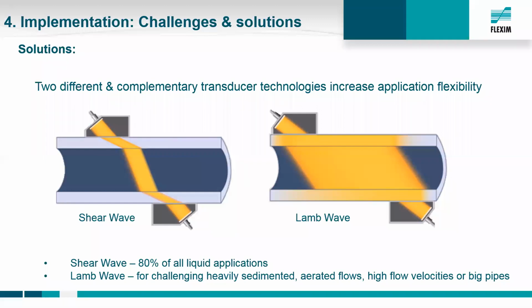As you can already read, the shear wave is usually the go-to technology or go-to technique for most liquid applications. And the lamb wave is rather used for gaseous applications. But from our experience, we can say that especially for very heavily sedimented or aerated flows or high flow velocities, especially in combination with big pipes, it is very beneficial to use the lamb wave, because sometimes the shear wave is limited then.